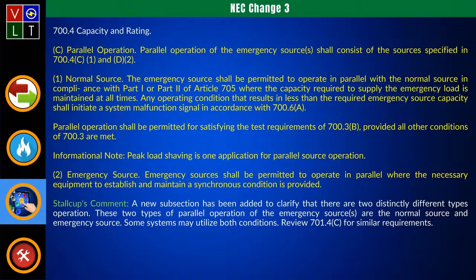It could be a little bit more clear, because what they're saying is it has to be in compliance with Part 1 or Part 2 of Article 705, but where the capacity required to supply the emergency load is maintained at all times. Now, if I go look at the emergency source, it just talks about the equipment necessary to establish and maintain a synchronous condition, which would be your normal operating condition. That's right. So they're taking that into consideration here, because they're saying where the capacity required to supply the emergency load is maintained at all times for the normal source. I think they did all right here myself, and that's why they allow parallel.